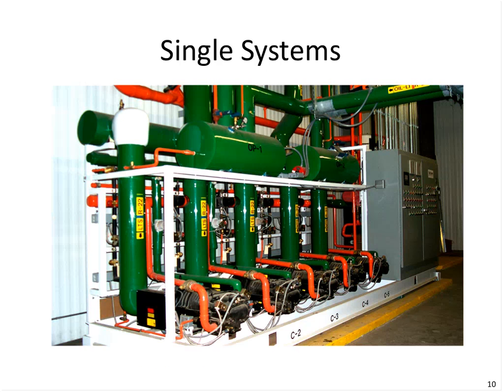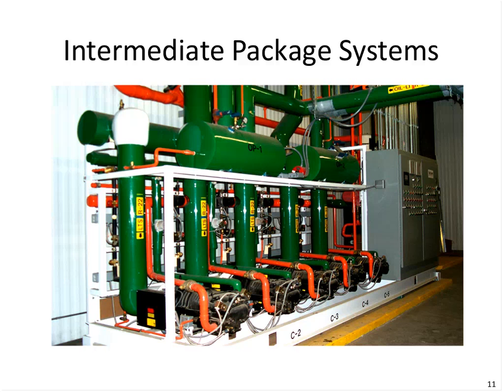We can take a look here at intermediate packages. There's some advantages to the intermediate package over, say, the single systems. It generally can have more efficiency built into it, often using an evaporative condenser or using water evaporating to condense the refrigerant. Disadvantages might be it takes a little more operator skill. These systems here, as you can see, the compressors, electrical equipment, all skid mounted, makes it difficult to expand the system. Once it's installed, to add more to it, not easily done. And generally, not using ammonia as a refrigerant.